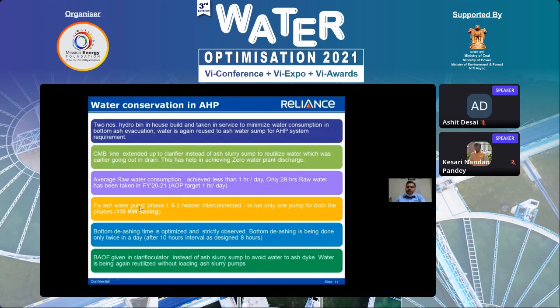We have the fly ash water pump, and we have phase 1 and phase 2. Phase 1 has 2 units of 300 megawatt, and phase 2 has 2 units of 300 megawatt. We have made a common header, and we are running only one fly ash water pump to cater our system, like bottom ash and de-ashing time. As per the standard OEM, 8 hours is the norm, but we are taking it after every 10 hours, for efficient utilization of our water.